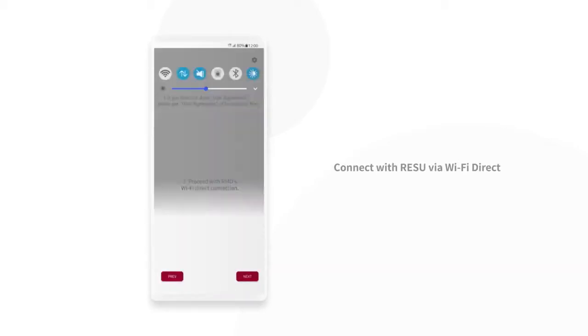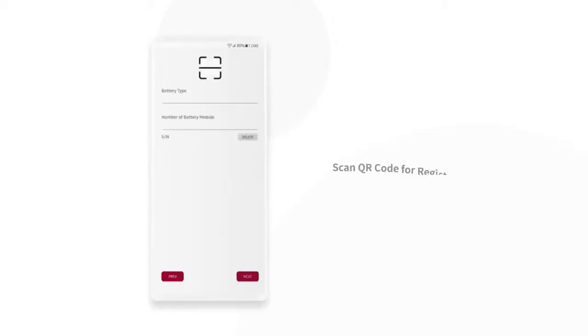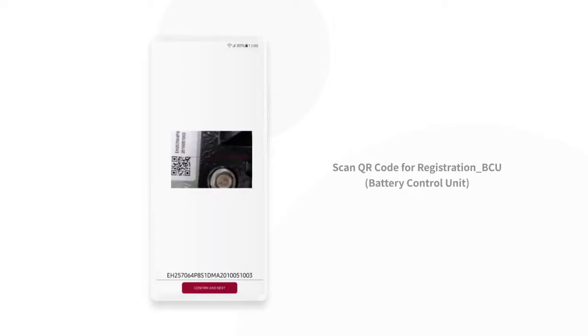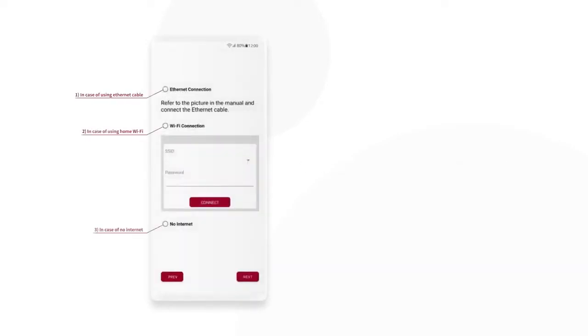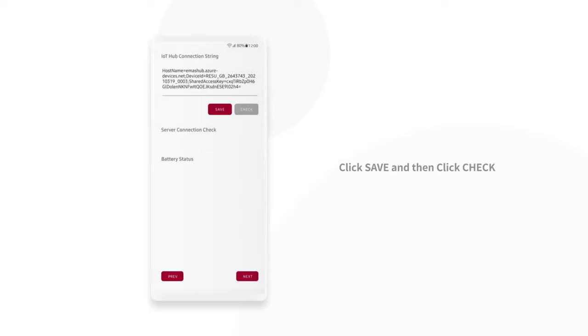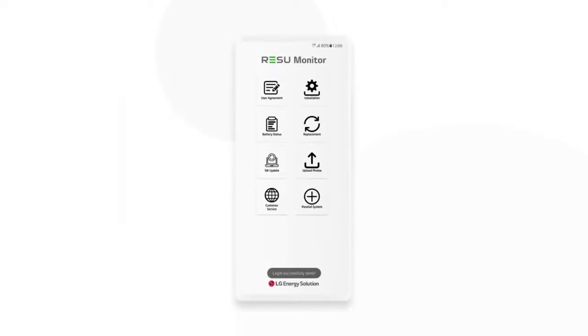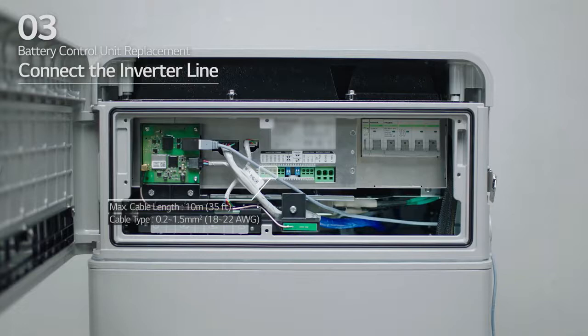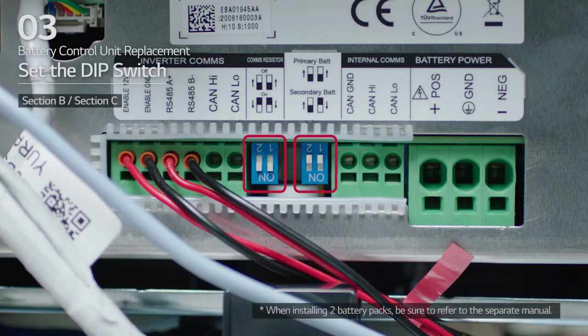Connect with RESU Prime via Wi-Fi and scan QR code on the battery modules and battery control unit. Next, connect the inverter line. For the inverter line, select the desired method for communications connectivity. Then, check that the DIP switch is set to their default settings.